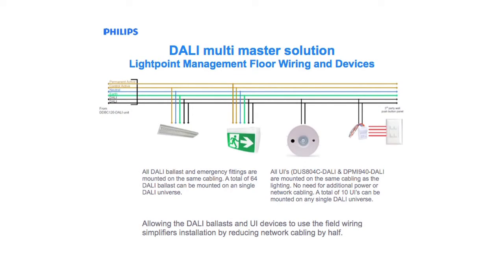I recommend that you never populate a DALI universe with more than 45 to 50 ballasts. This allows for additional ballasts to be installed after the project has been complete. It is very simple to install an additional ballast or 2 into a network that has not used all DALI addresses. It is very difficult to run an additional DALI network in a completed network.